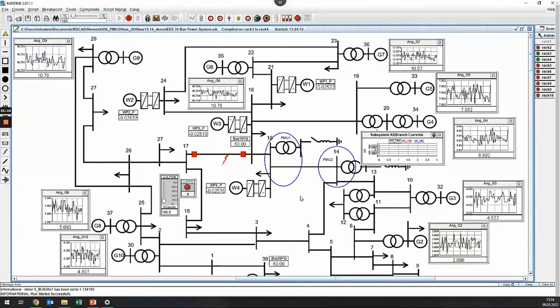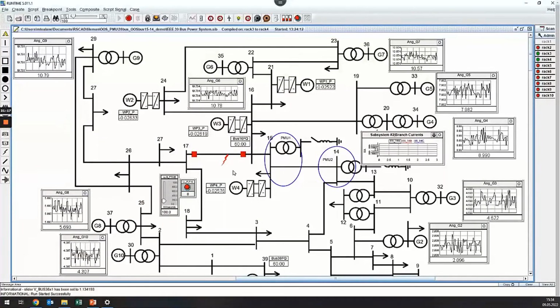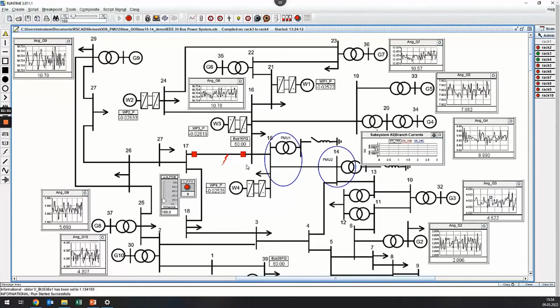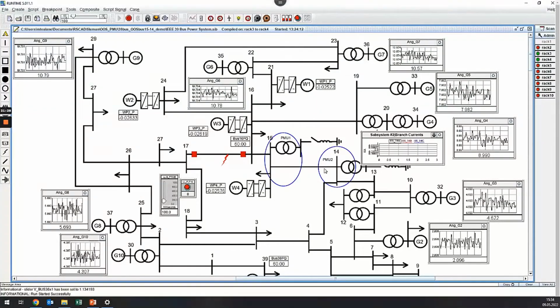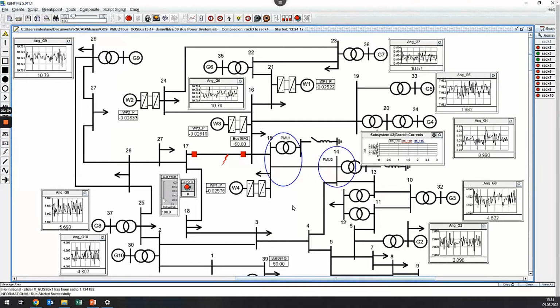We will initiate an out-of-step condition by applying a three-phase fault on line 16-17, after which the line gets disconnected from the network and power swings take place in the transmission line remaining connecting the two parts of the network.